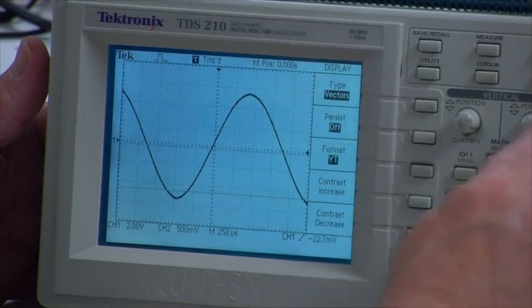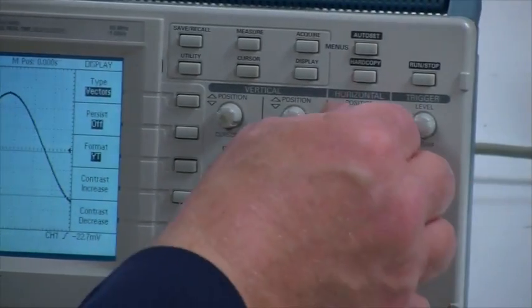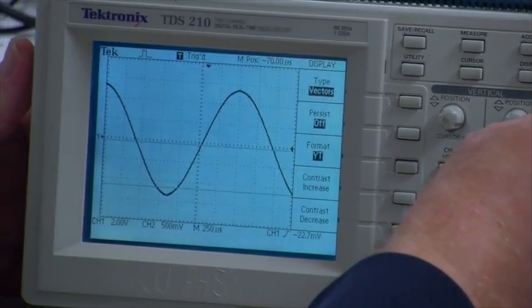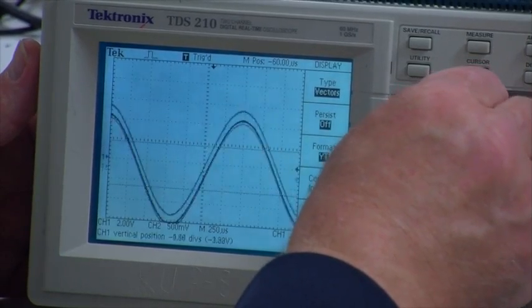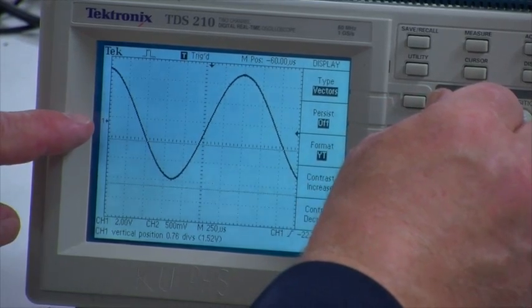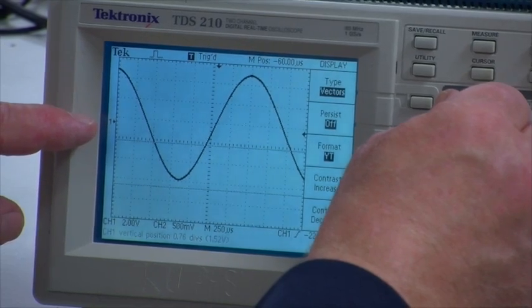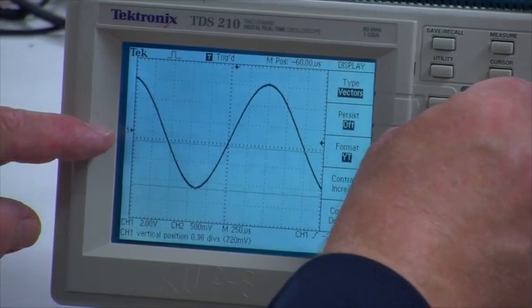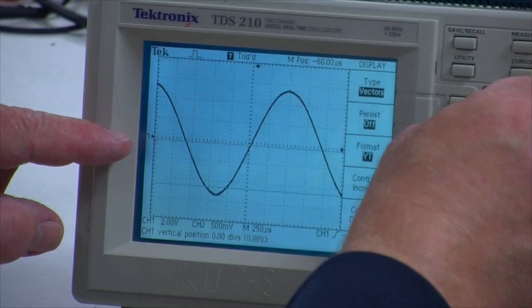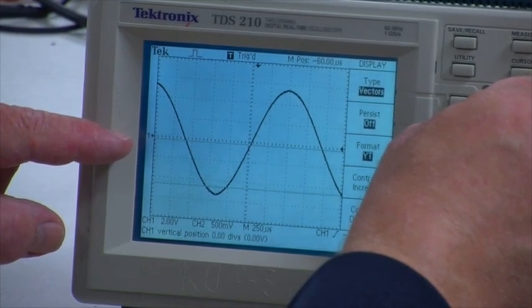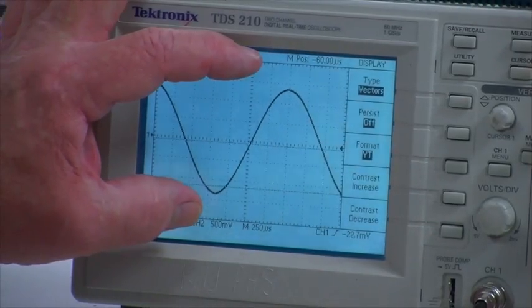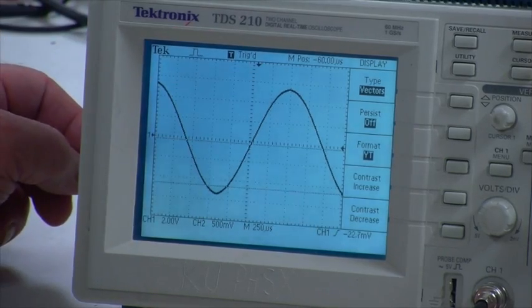All of these have position knobs. In the horizontal case, it'll move the signal left and right. In the vertical case, it'll move the signal up or down. There's a number and an arrow, in this case number one, and that tells us where the zero point of the signal is. A lot of times we'll want that set right on the x-axis so that the signal is centered on the screen.